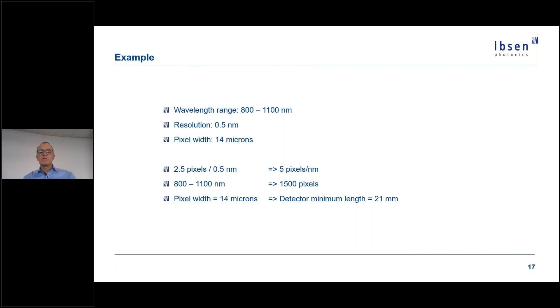In a spectrometer, the optics is in fact creating an image of the slit onto the detector, as shown here. If we change the optics, we can change the magnification in the system and thereby magnify or demagnify the slit image on the detector. But as mentioned earlier, we want the slit image to cover around 2.5 to 3 pixels.